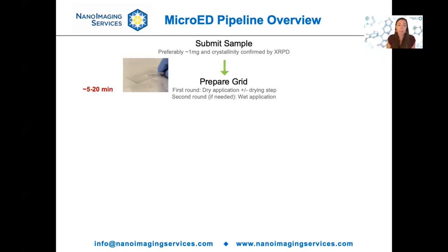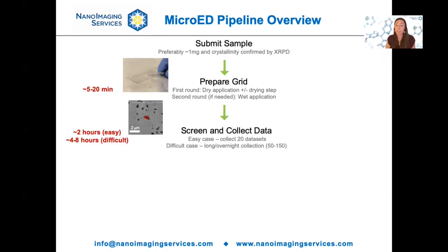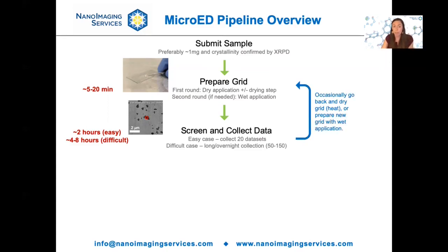Here at Nano Imaging Services, we've built a micro-ED pipeline for small molecule structure determination. This starts with clients submitting about a milligram of powdered sample, and we ask that clients confirm the sample is crystalline using powder diffraction if they're able to. We then prepare a grid, typically by dabbing a TEM grid against a pile of powder and tapping off the excess. We place this into a Glacios microscope — a 200 kilovolt microscope equipped with a Ceta-D camera — and use our automated software to screen for crystals and collect diffraction data. For an easy case, we collect about 20 data sets in roughly two hours; for more challenging cases, we set up an overnight collection of about 150 data sets in eight hours.